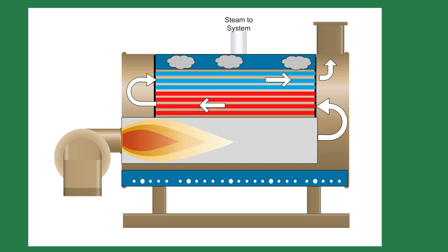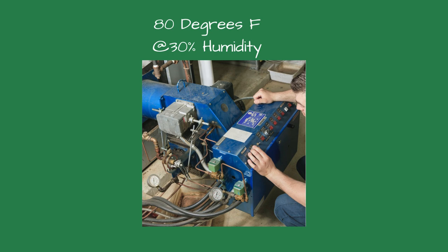Understanding how combustion air temperature and humidity affect boiler efficiency can help operators optimize performance, reduce fuel consumption, and lower emissions. Most boilers are tested using 80 degree Fahrenheit combustion air with a relative humidity of 30 percent — typical conditions found inside a boiler room.